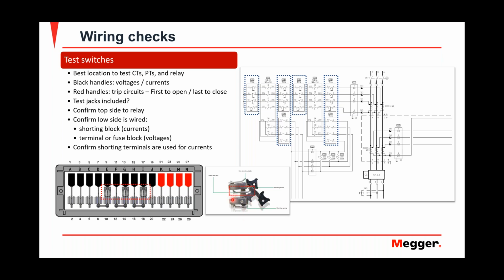So one thing to keep in mind is, especially for currents, make sure that the top wires go to the relay and the bottom of the test switch goes to your CTs. For voltages, it's not that important, but at least for currents, it's imperative that the top goes to the relays and the bottom goes to the CTs, because that's the way physically the test switch is being used and how it's being shorted. Confirm that the shorting terminals are used for currents and the voltage terminals are used for voltages.